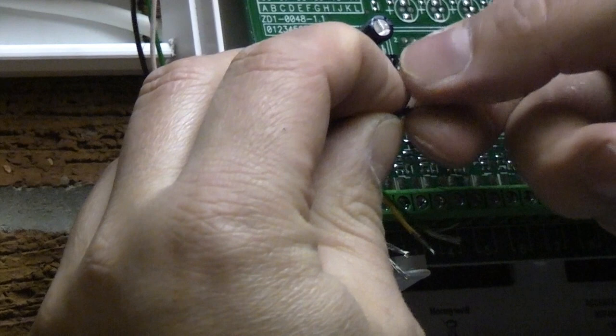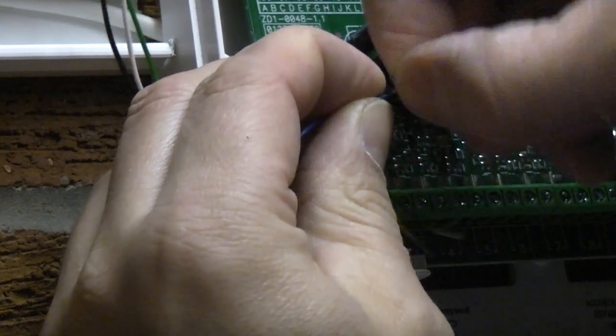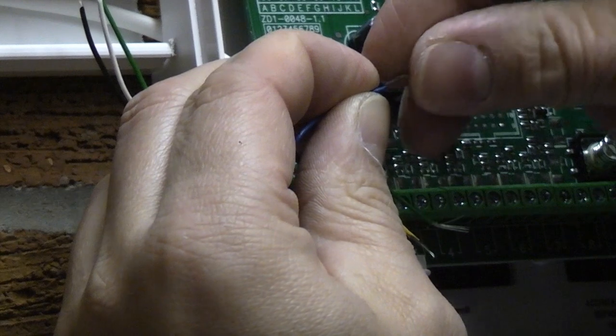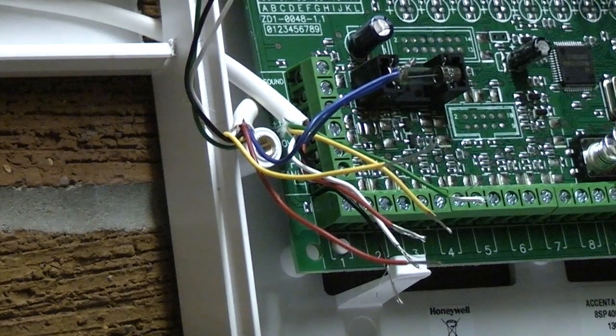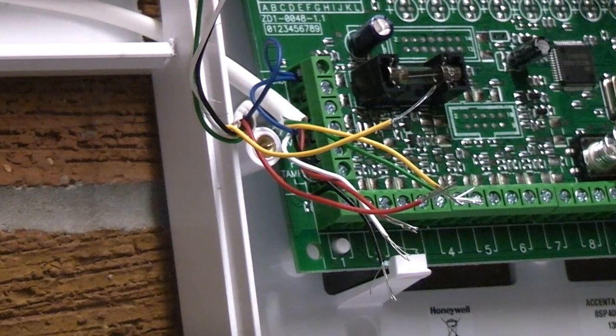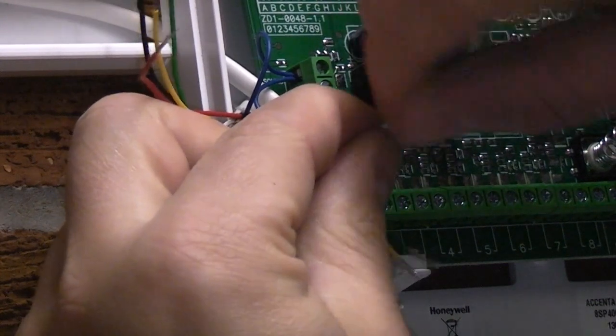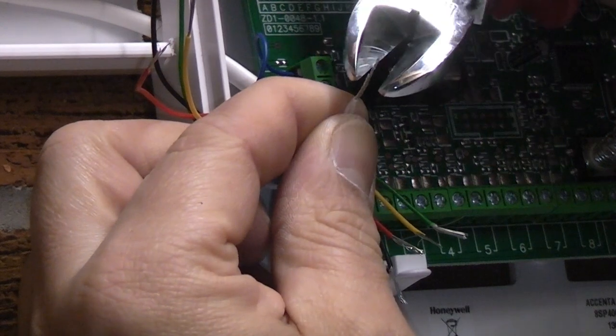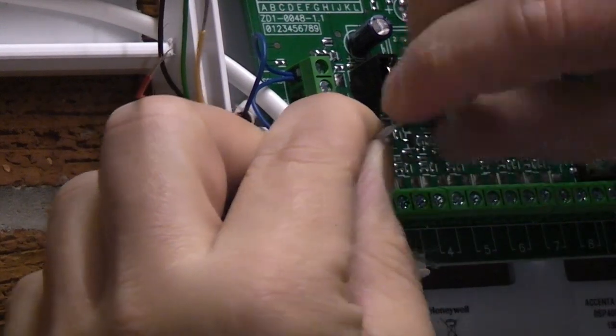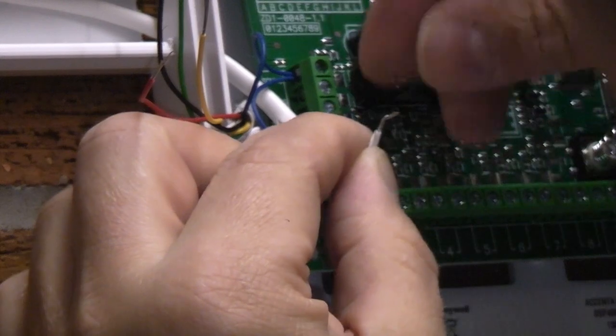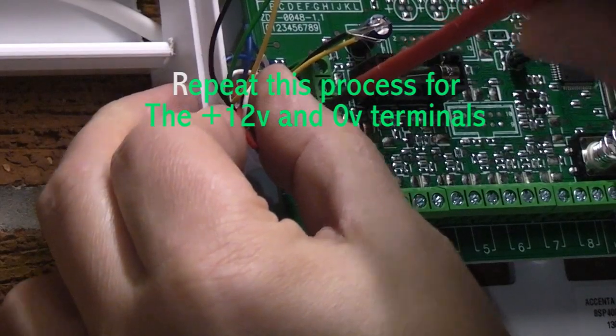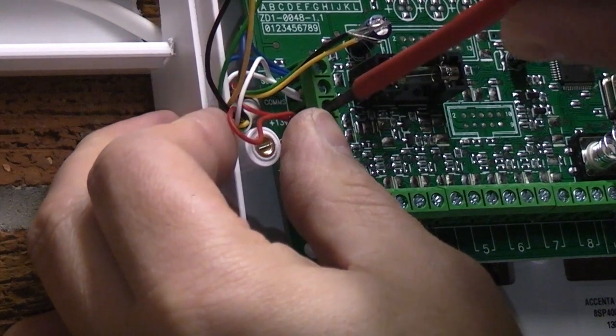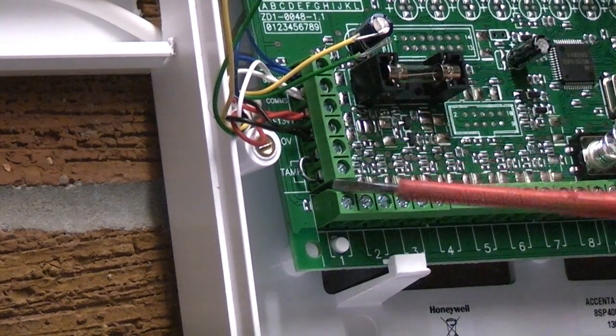We're going to fold the conductor back on itself and then terminate that into the terminal. We're now going to do the comms terminal which is the two white wires, so we're going to put them both together and twist them. That might actually be a bit long so we're just going to snip a bit off that. Then we'll fold the conductor back on itself and insert that into the terminal and tighten that up. We've now got the sound, comms, positive and negative wired into the remote terminal.